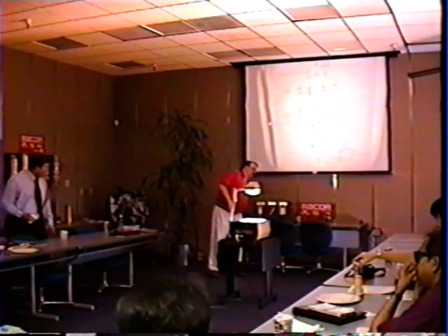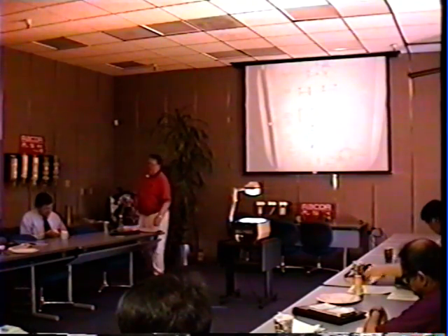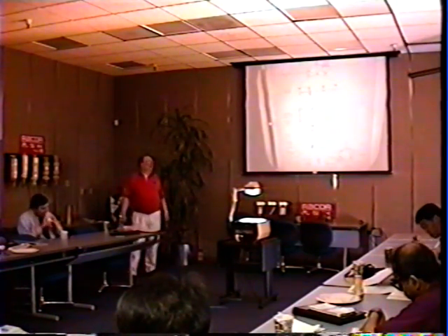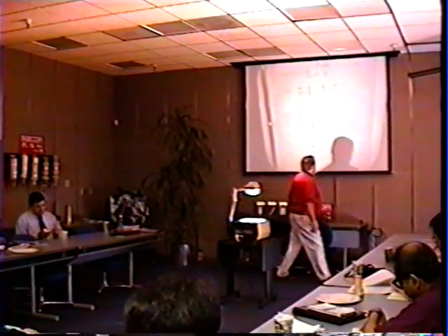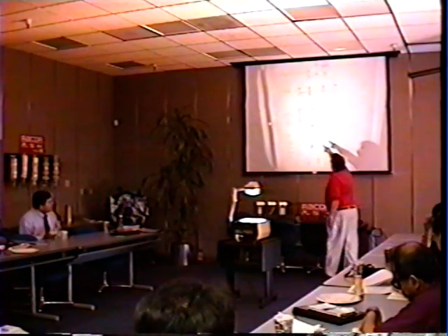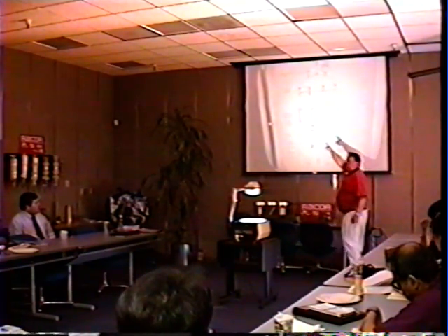Now, how efficient is it supposed to be? 0.3 micron to 3 micron? About 99%. So very efficient. Okay, now, second stage, our separator, we are flowing outside in.